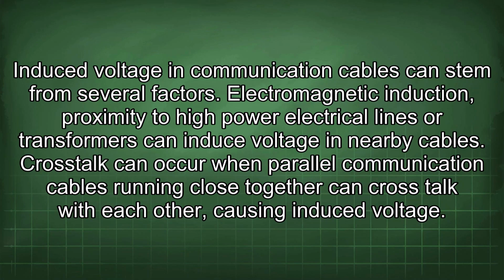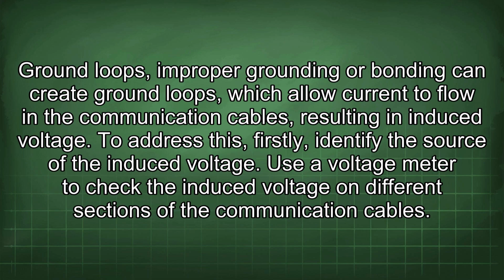Induced voltage in communication cables can stem from several factors. Electromagnetic induction: proximity to high-power electrical lines or transformers can induce voltage in nearby cables. Crosstalk: parallel communication cables running close together can crosstalk with each other, causing induced voltage.